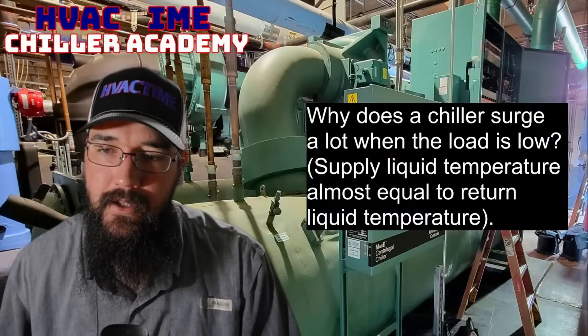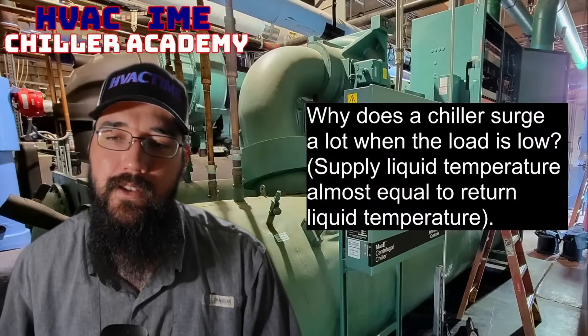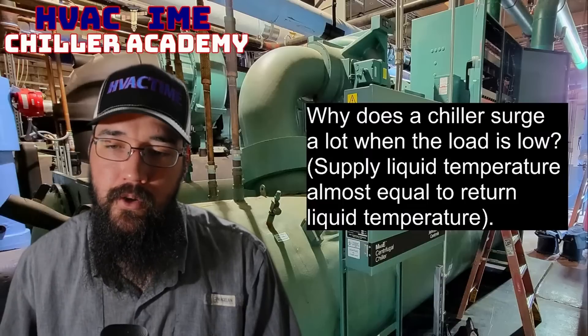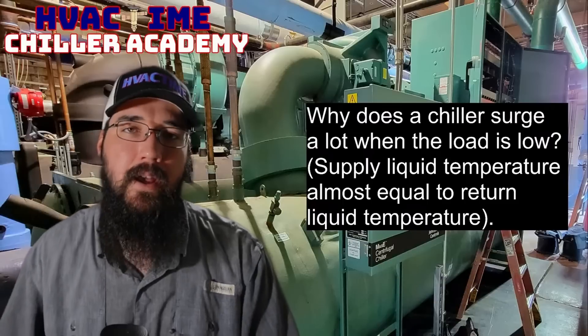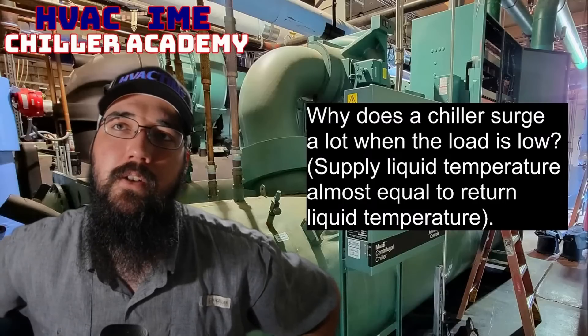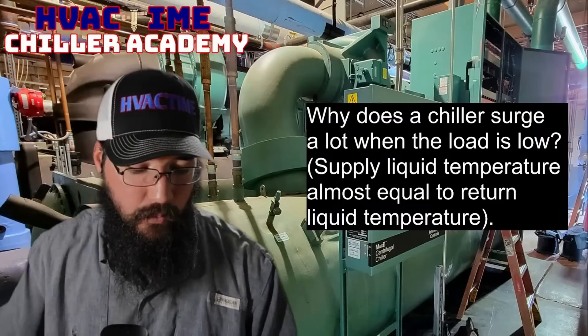Why does a chiller surge a lot when the load is low? Supply liquid temperature is almost equal to return liquid temperature. This gets back to controlling our lift and how much the compressor can ramp.